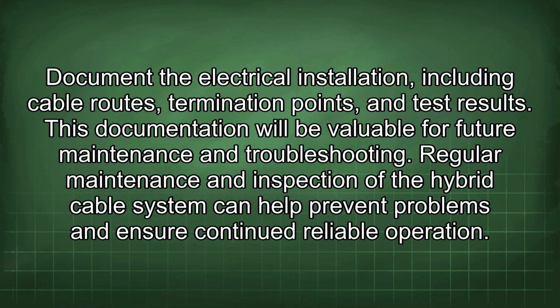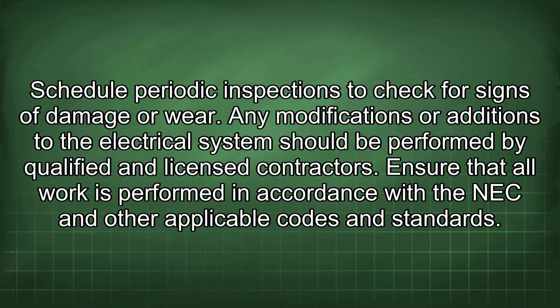Document the electrical installation, including cable routes, termination points, and test results. This documentation will be valuable for future maintenance and troubleshooting. Regular maintenance and inspection of the hybrid cable system can help prevent problems and ensure continued reliable operation. Schedule periodic inspections to check for signs of damage or wear. Any modifications or additions to the electrical system should be performed by qualified and licensed contractors. Ensure that all work is performed in accordance with the NEC and other applicable codes and standards.